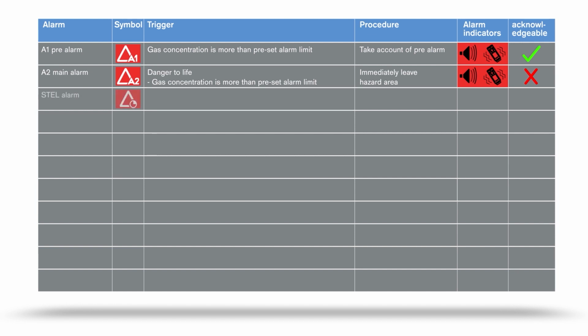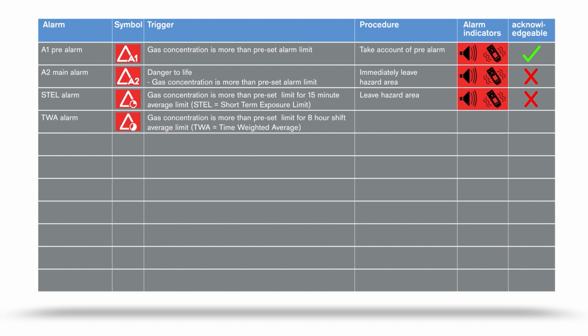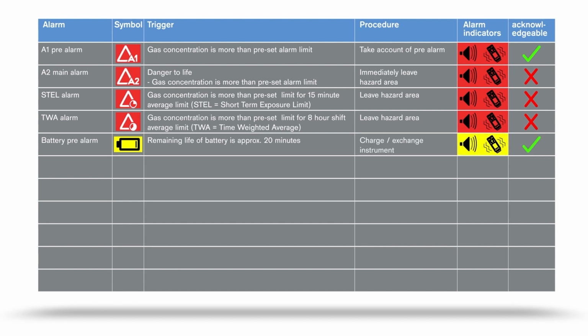The STEL alarm, short time exposure limit, indicates that a gas concentration has exceeded an average value of 15 minutes. Leave the hazard area immediately. A TWA alarm, time weighted average, sounds when an average value, calculated from an 8-hour shift, is exceeded. You must leave the hazard area. The battery pre-alarm is triggered when the device battery has approximately 20 minutes remaining. The battery main alarm signals that the battery has reached the end of its capacity. The device then switches off automatically after a few seconds.